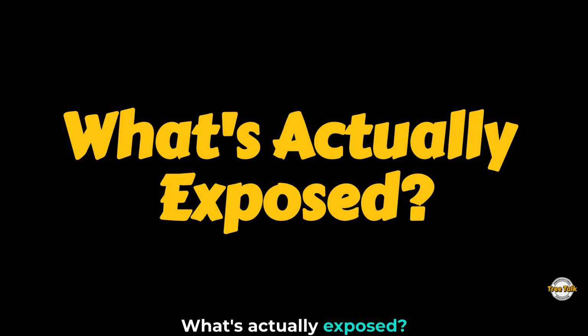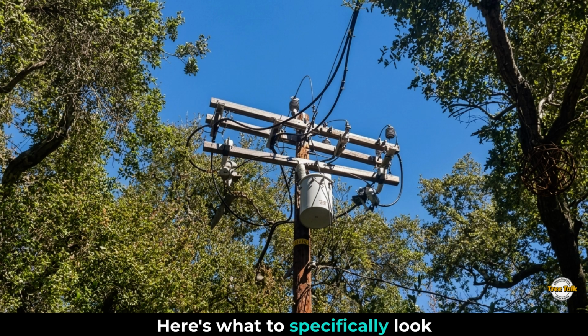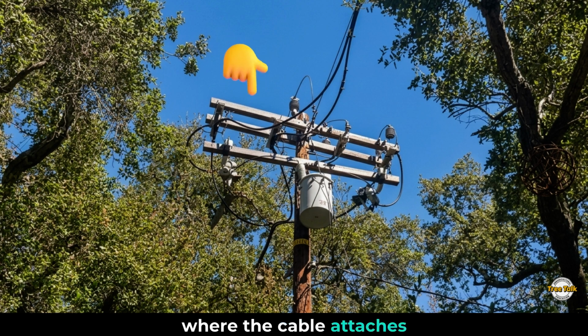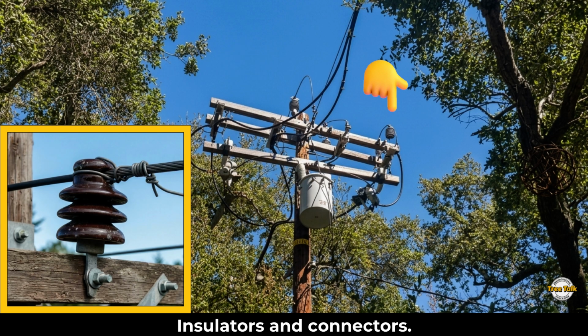What's actually exposed? Here's what to specifically look for at every pole where an aerial cable system connects. Crossarms, where the cable attaches or is dead-ended. The crossarm hardware itself is bare metal, and a branch resting against it is resting against energized equipment. Insulators and connectors. The point where the covered conductor's jacket ends and it clamps into pole hardware is a bare connection point, even though a few feet of wire on either side is insulated.